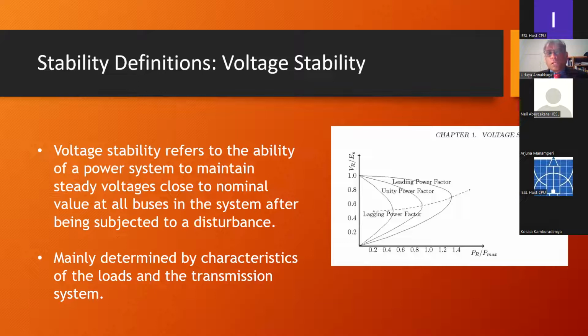But what happens with dynamic loads is, although the consumption decreases instantaneously or almost instantaneously when the contingency happens, dynamic loads will try to pick up the load to the previous levels. So in that process, it might drive the network into the maximum power transfer capability limit. And if you reach that point, then the next thing that can happen is voltage collapse, voltage instability.